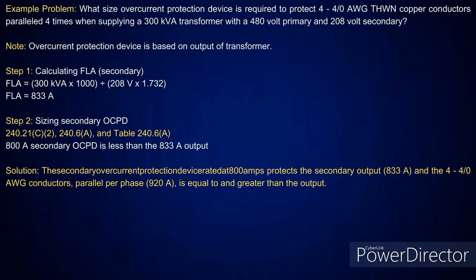Here, I'm dropping into 240.21(C). This is transformer secondary conductors, and all you're doing is calculating the transformer. We did this the other day, when we first started, where you had a transformer and we were doing basic calculations. I said, just get the kVA of the transformer, divide it by the voltage, and that's your amperage. Same thing here. We're sizing the overcurrent protection devices based on the output of the transformer.